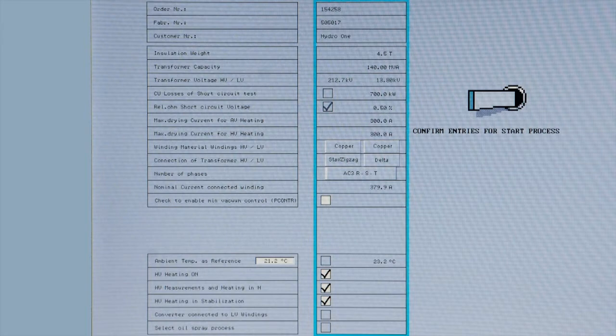If the LFH process is combined with an oil spray process, this box must be checked. Then, different parameters will be considered in the process. It is of utmost importance that these data are correct since the converter will calculate the current and voltage based on this information. Wrong data can result in damage to the transformer. After these data have been confirmed, then the virtual switch is set to the green position.